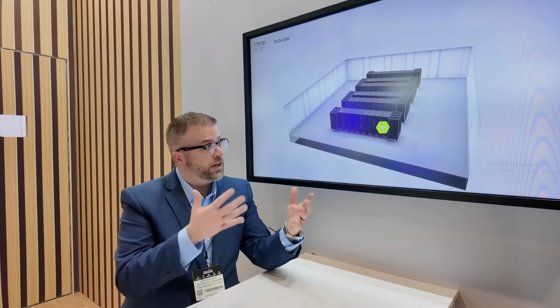So the TCDU Series is a centrifugal water-based pump specifically designed for direct liquid cooling in-rack solutions. We can show a little bit of what the TCDU looks like if we have some time to get through that. So here we start at the room level, going down to the CDU level. And what we have done, the TCDU Series is based on an N+1 redundancy. So we do have one pump active, one pump sitting in lieu, waiting to be turned on as it is required by the system itself.